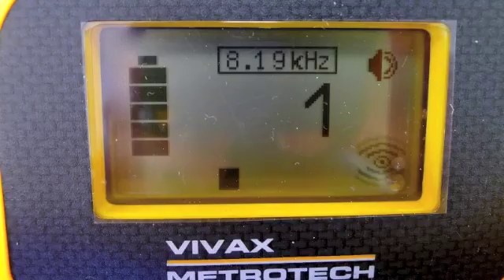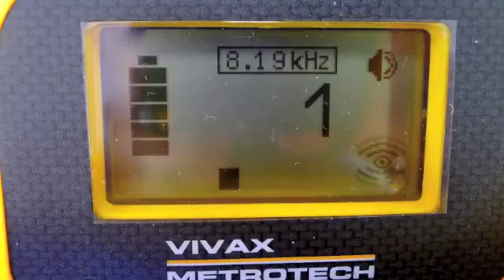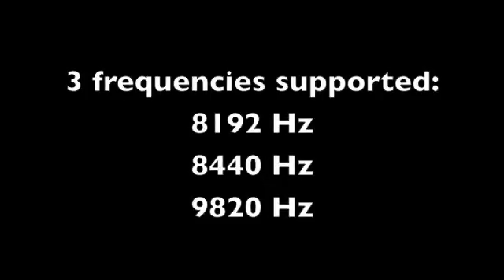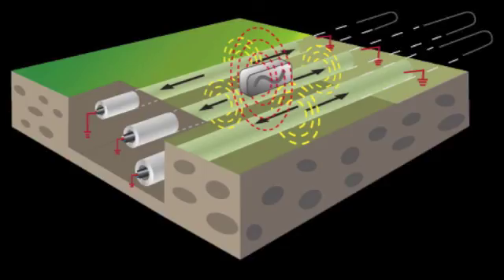Again, the transmitter will recognize that it has no cables connected and will activate induction mode. Only three frequencies are available, the same as using a clamp. This method is not recommended, as an induced current can easily couple to other metallic lines and structures adjacent to the target line.